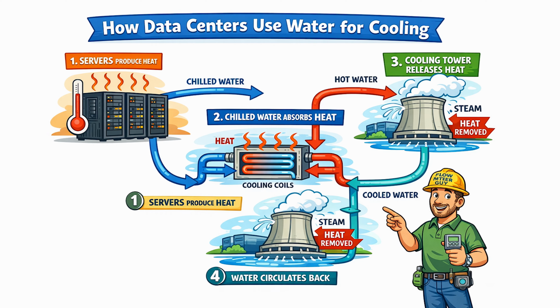Here's how that works. Inside the building, chilled water flows through cooling coils of heat exchangers. As warm air from the servers passes over these coils, the heat transfers into the water. The water absorbs the heat and carries it away through piping systems, and now the water is hot.